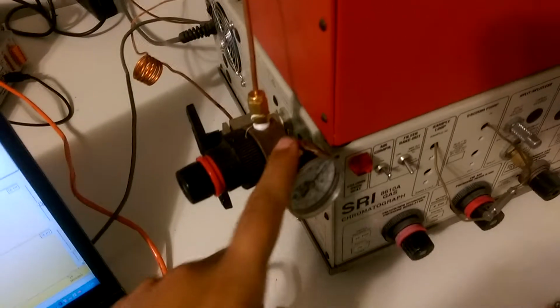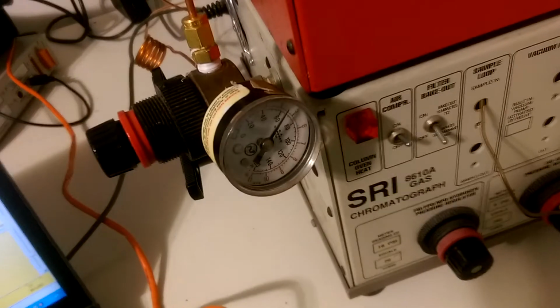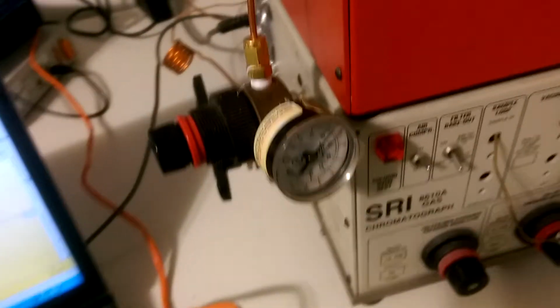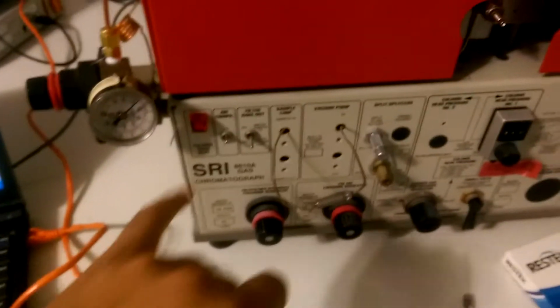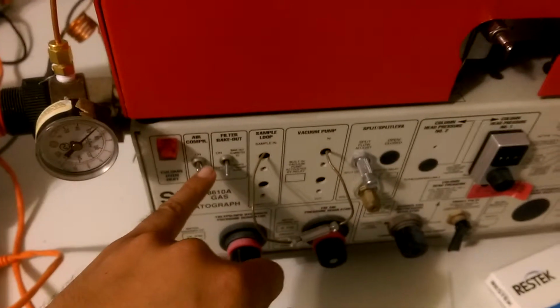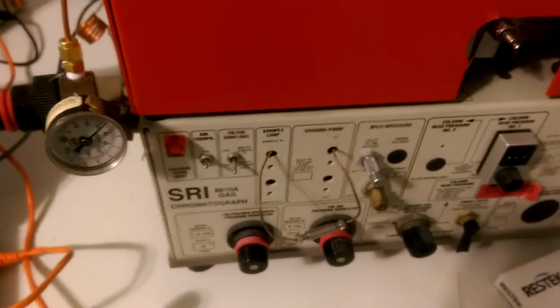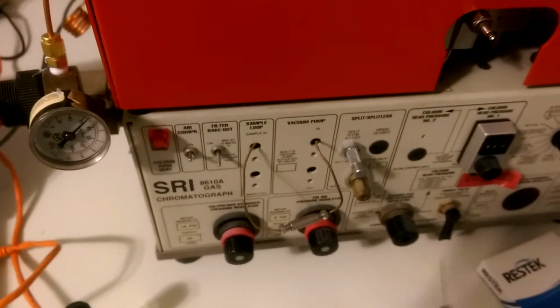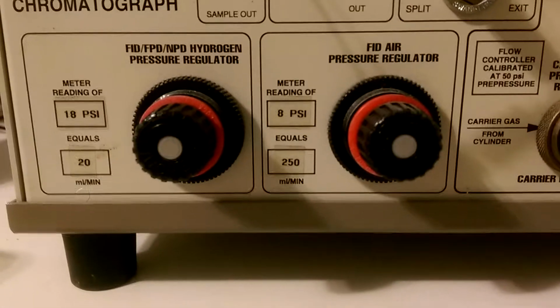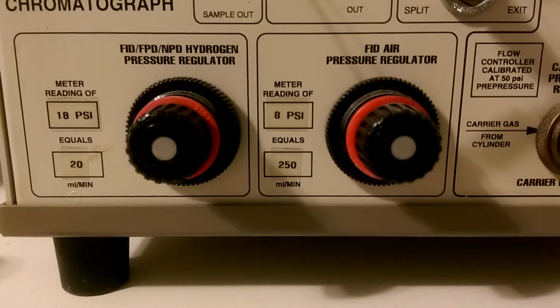The gas connections are to the side of the unit. The helium carrier gas includes its own separate gauge, so you can check right at the source, around 60 psi here. And then we have a hydrogen inlet gauge here for the FID detector. The unit conveniently has its own air compressor, which provides the air for the FID. So no need for a separate cylinder for that.